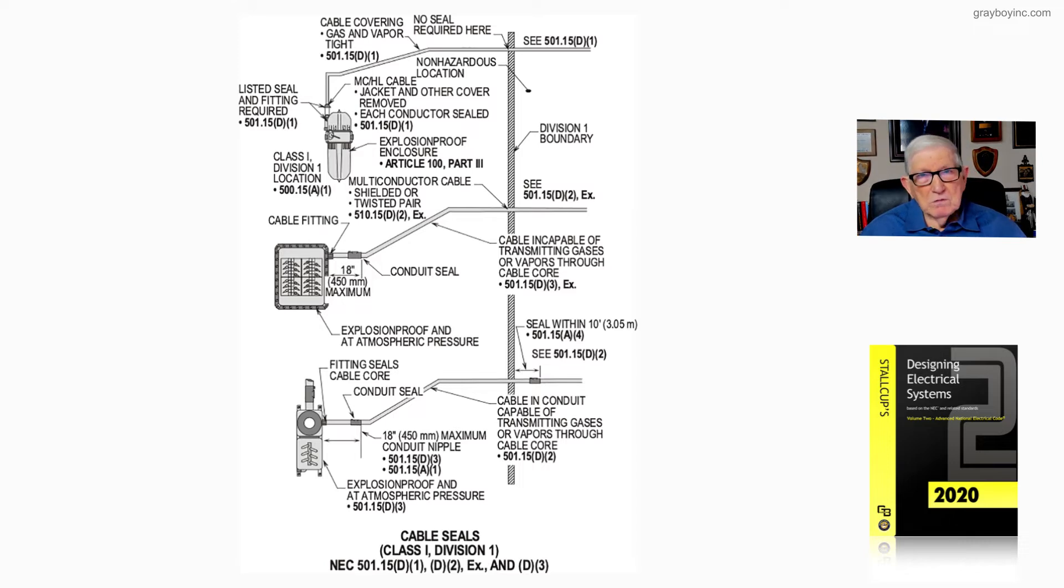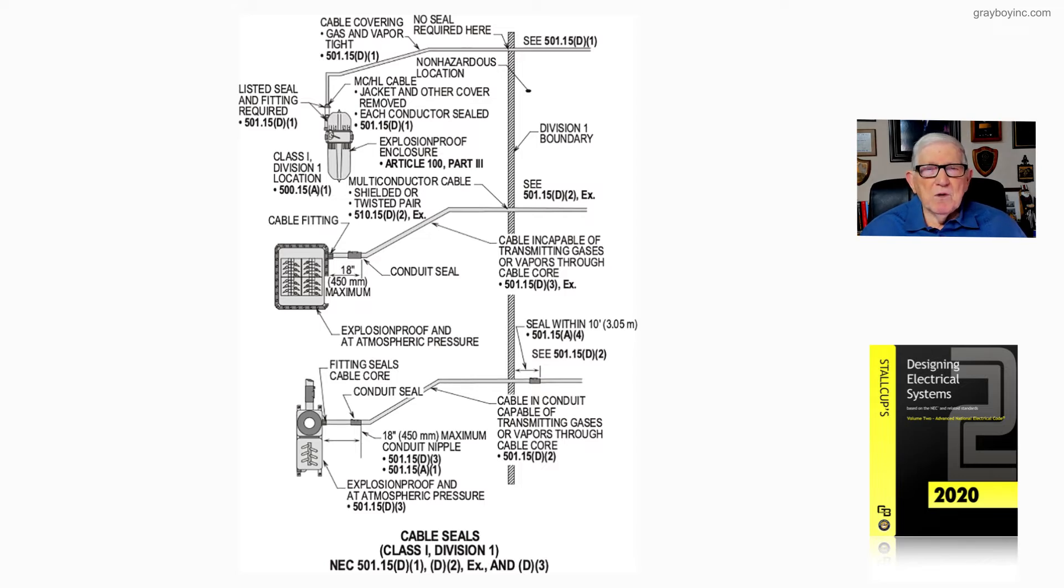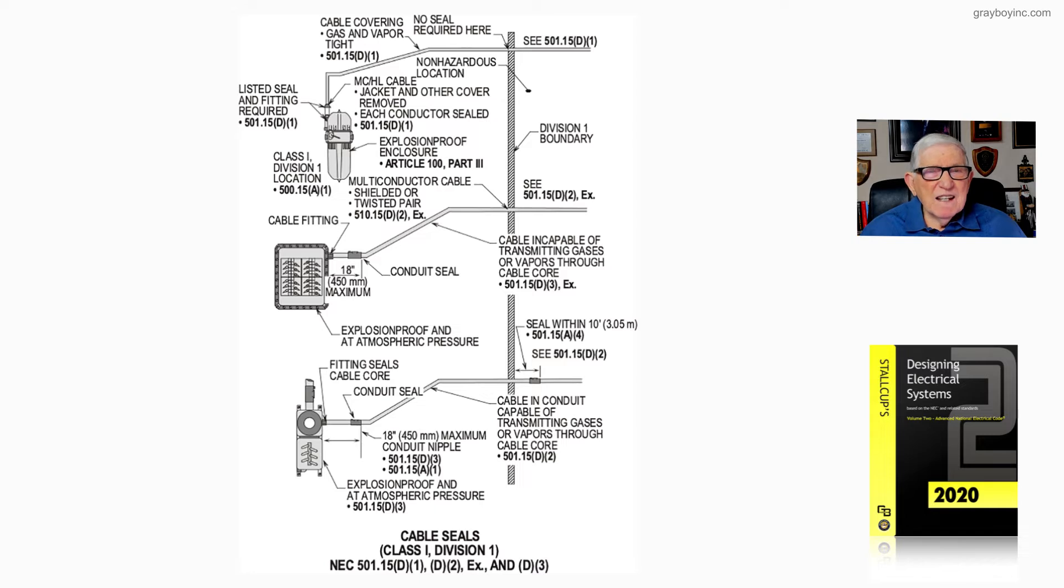Anytime we use a cable, we've got to review it and see if the cable is capable of passing vapor through the core or not. We have to review that based upon the cables, and 501.15d and e would be what we review very closely.